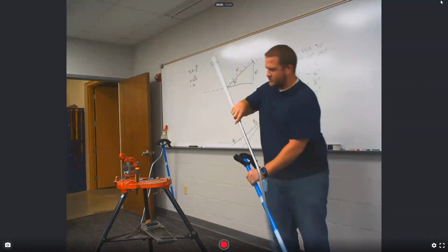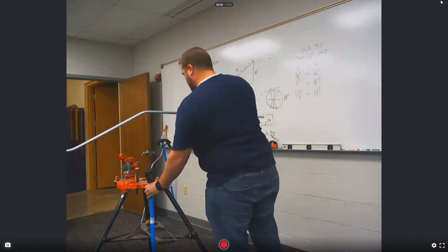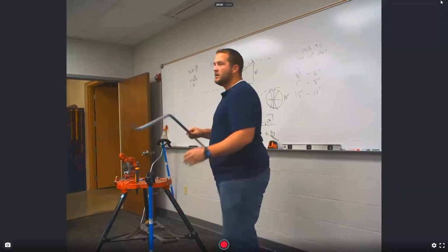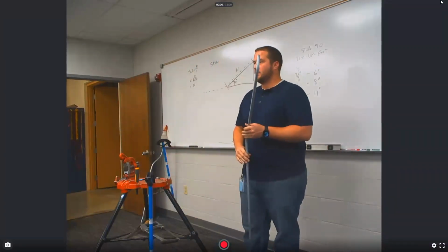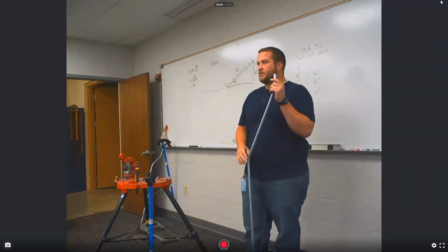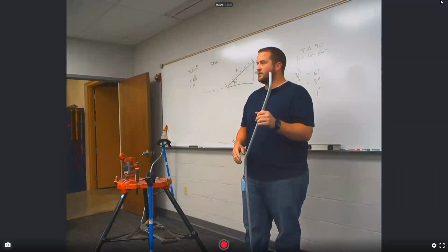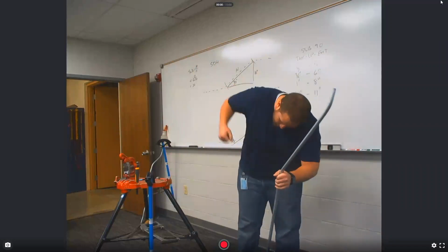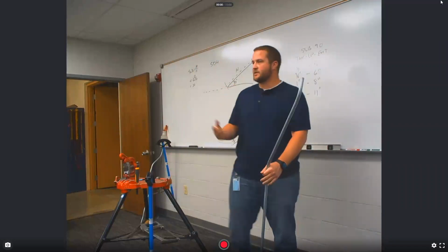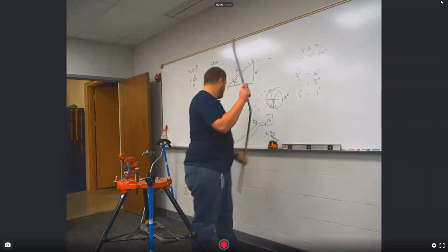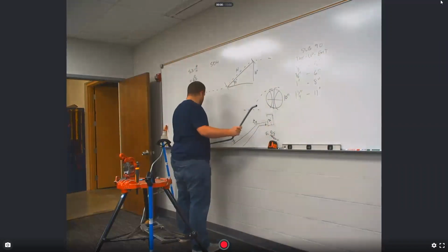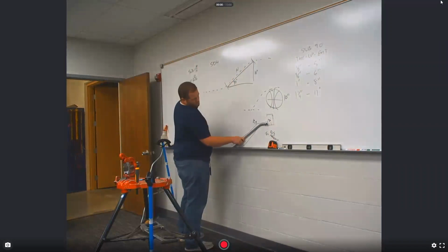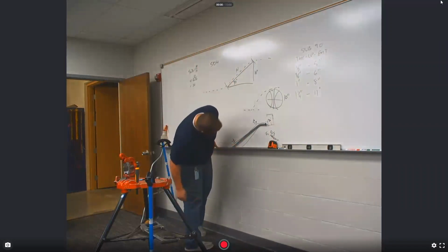When it's 30 degrees, you don't really have to put it on the ground. No, 30, 45, 22 and a half, none of them. You should do them all from the air, because you can look and see what you're bending to when you're doing it. If it's on the ground, you can't see what you're doing.